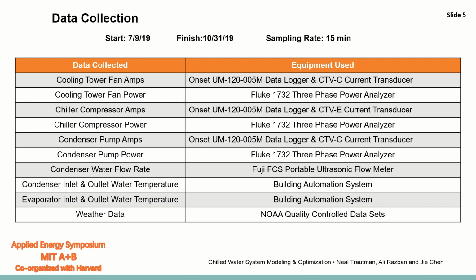So in terms of our data collection, we started on July 9th, 2019. We finished on October 31st, 2019. We used a sampling rate of every 15 minutes. In the table, you can see an overview of the data that we collected and the equipment we used. We used a combination of data loggers, current transducers, 3-phase power analyzers, a Fuji portable ultrasonic flow meter, some of the data we collected using the building automation system, and finally we got our weather data using NOAA quality controlled data sets.